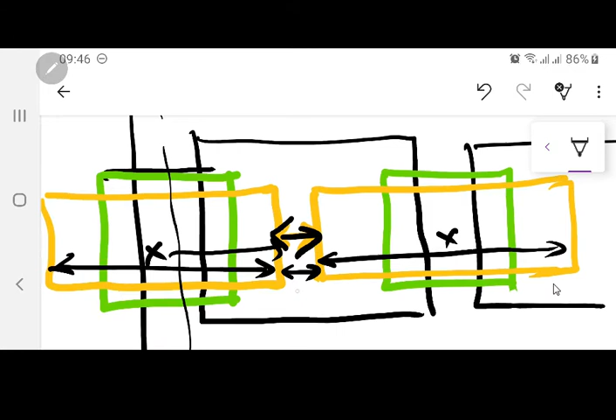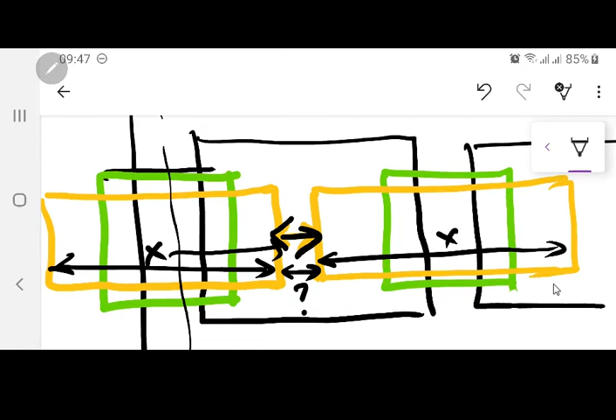Here this is kept in this 100 kV transformer as approximately 13 mm, okay? So this can also be a variable. But the problem is this - if you reduce it down at high voltage, and if there is a spike, a switching spike, or an insulation strength issue or spike over there, there is going to be a flashover or a dielectric failure, which means the two windings are going to start to conduct through the oil.